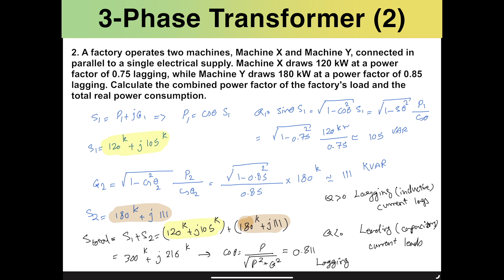So essentially, the combination of a power factor of 0.75 and 0.85 turns out to be around 0.81, somewhere in between them. That's how we get the total power factor with respect to individual power factors and the calculation of the apparent power as well.